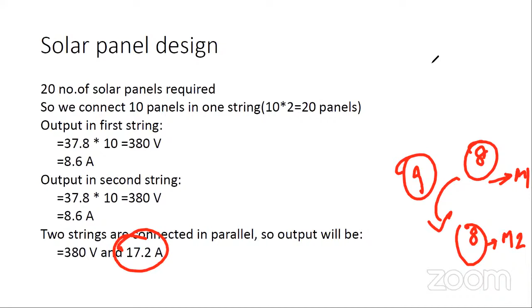Okay. So that is how you are verifying for the first string and second string. And even if you connect two strings in parallel, for the individual MPPT, it is not going to be more than 9 amps, because the short circuit current of the PV module is only 8 amps. Each is given to a single MPPT. So 8 amps is going to MPPT 1 and another 8 amps is going to MPPT 2. Even if both get combined, the current is 17.2 amps. The maximum current the inverter can accept for the string is 19 amps. So that is also within the limit.